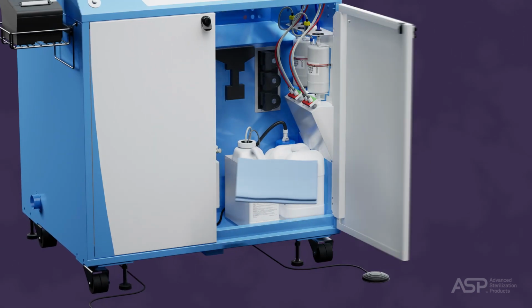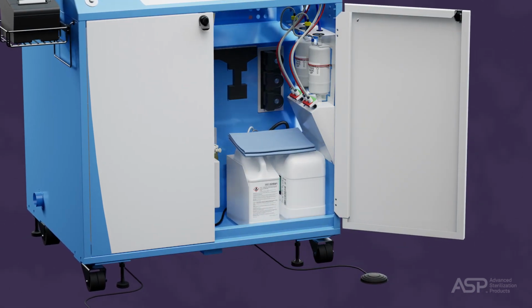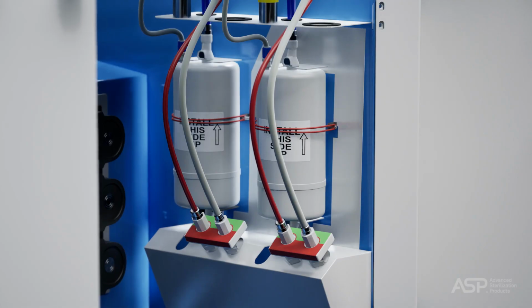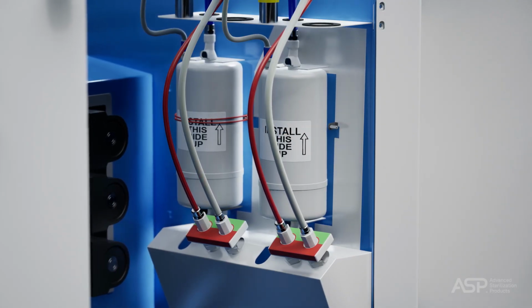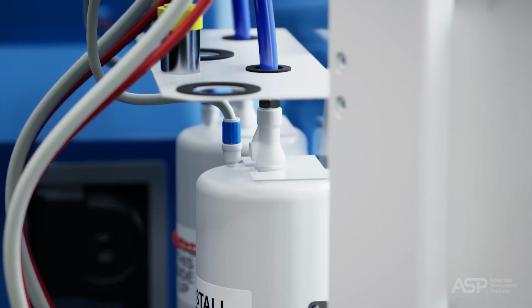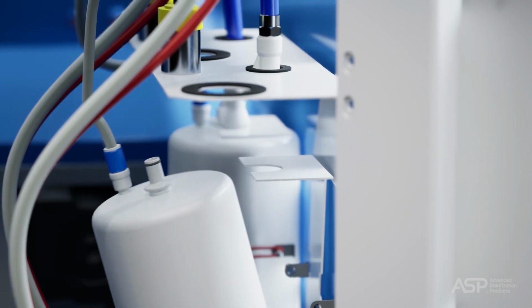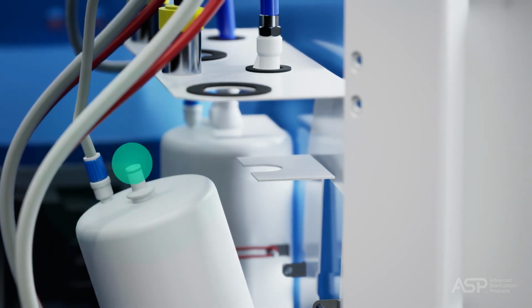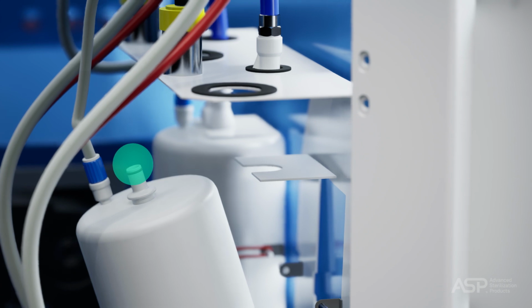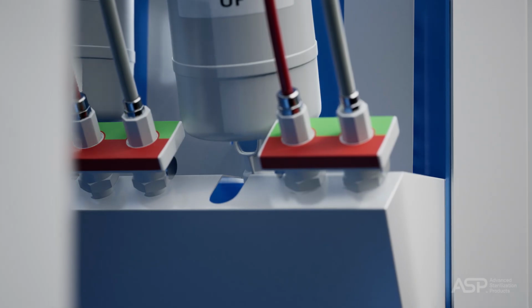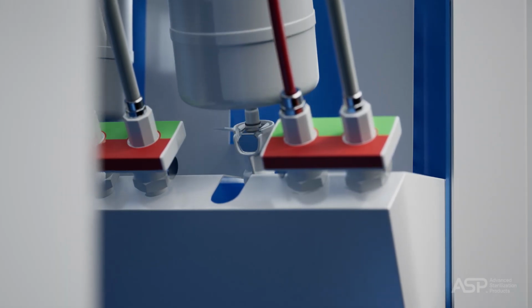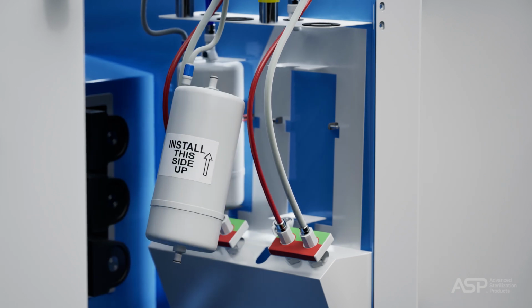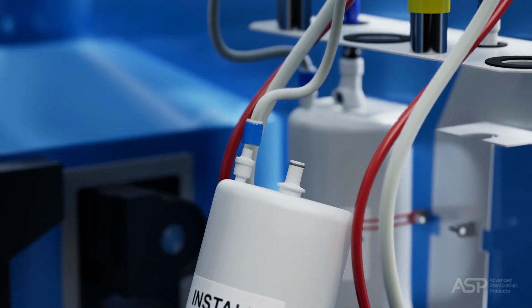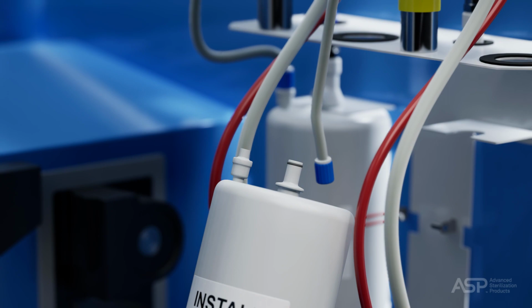Wearing PPE, place towels or absorbent cloths to absorb any dripping water. Unhook the rubber band holding the filter housing and unfasten the top quick disconnect by pulling it up. Place your finger over the hole and continue to hold your finger over the top hole. Unfasten the bottom quick disconnect by pulling it up. A small amount of water may drip. Unfasten the twist connector on the top front of the filter.